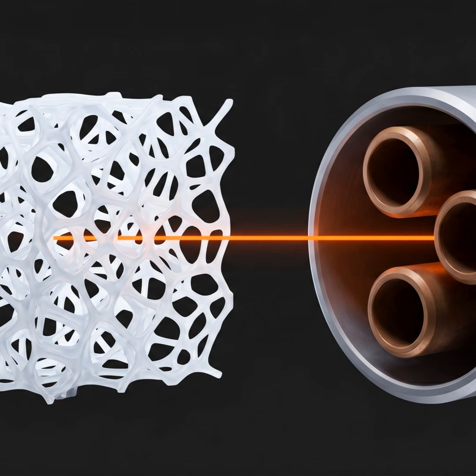You can prove mathematically that this specific pipe is outputting a sustained flow of refrigerant at 200 to 250 degrees Fahrenheit. You capture the exact telemetry of their waste. Then you ask the facility manager for one piece of financial data: their monthly boiler fuel consumption, basically how much they are paying the gas company every month.